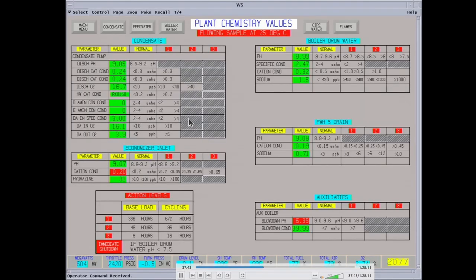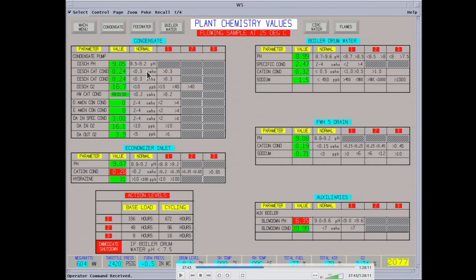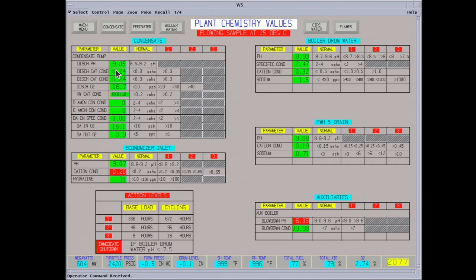Here's the lab, which is critical for water chemistry. On the water chemistry screens, pH is critical. You look at cation conductivity — you're really worried about sodium and silica in your steam, which can plate out on your turbines and create a lot of problems. Dissolved oxygen is a big one. You're mostly concerned with pH, conductivity, and oxygen. This can tell you if you have a feed water leak — if you start getting high conductivity, you know you have a tube leaking and raw water is dumping in.